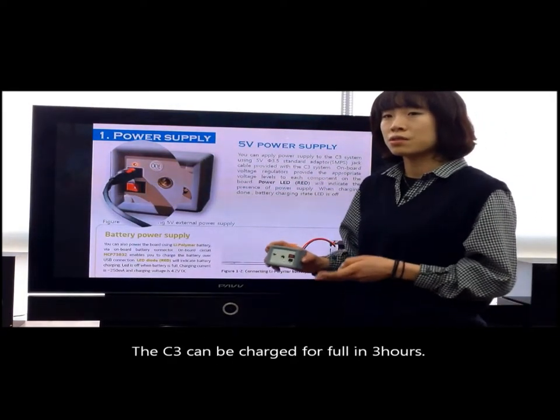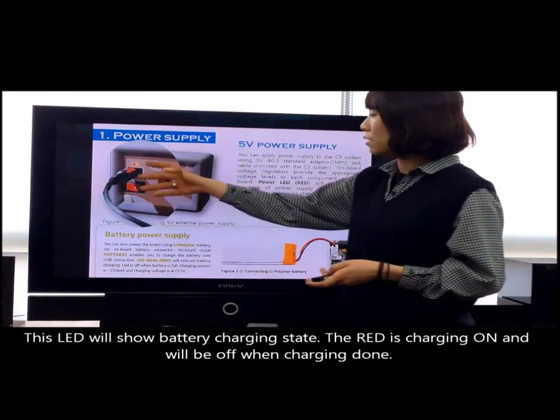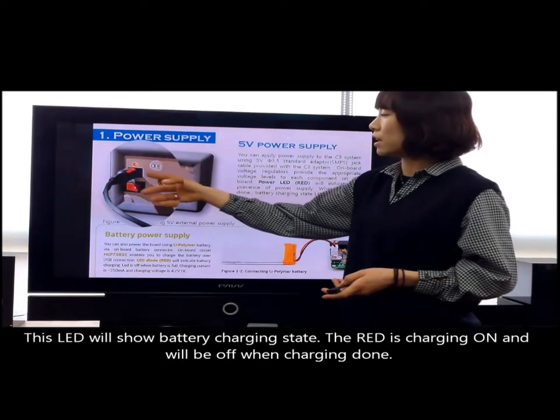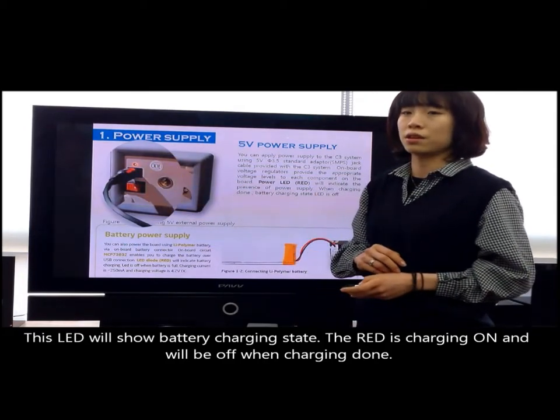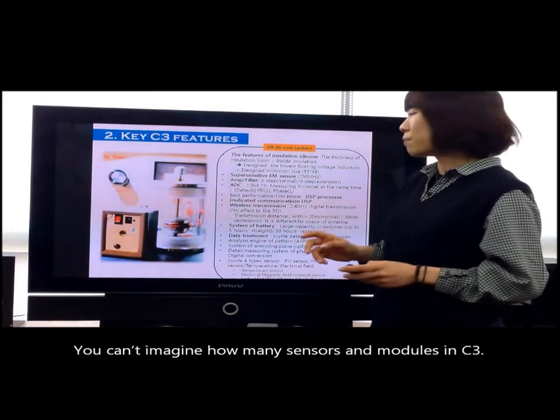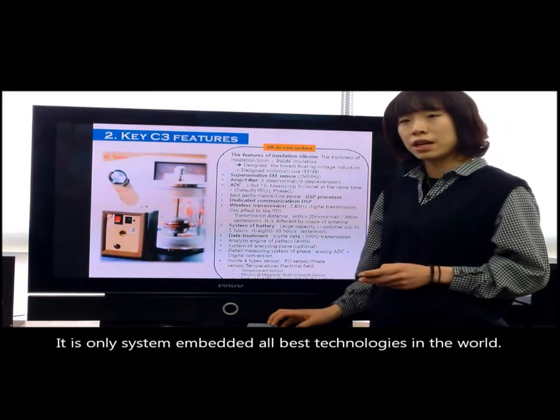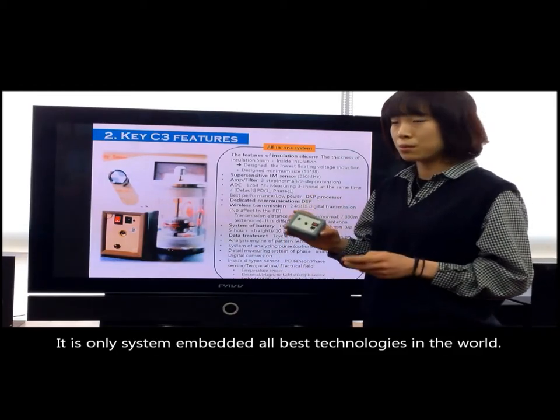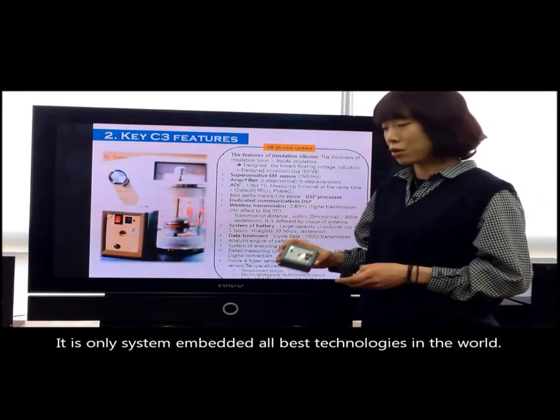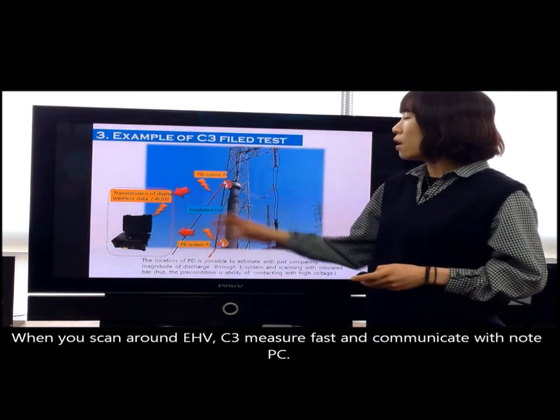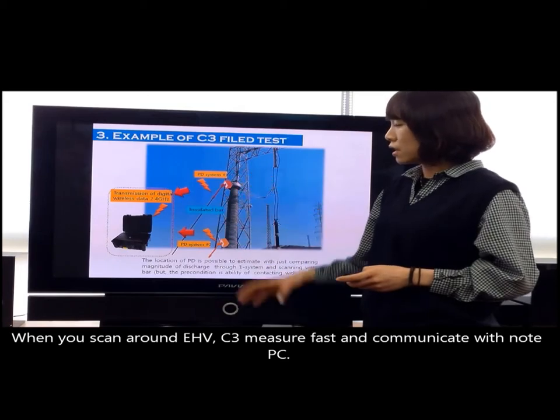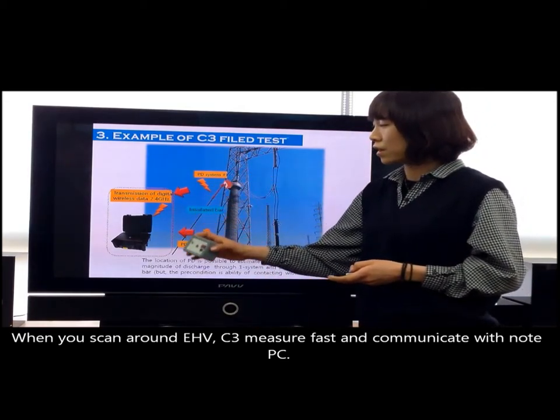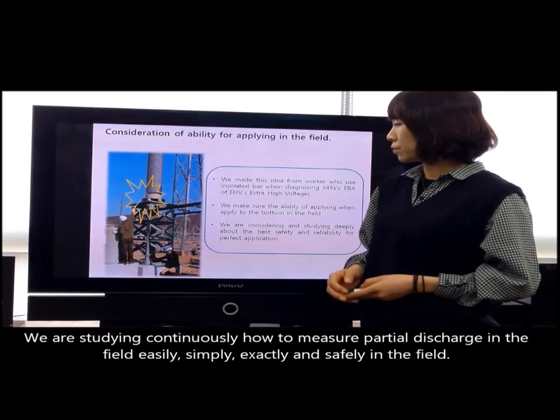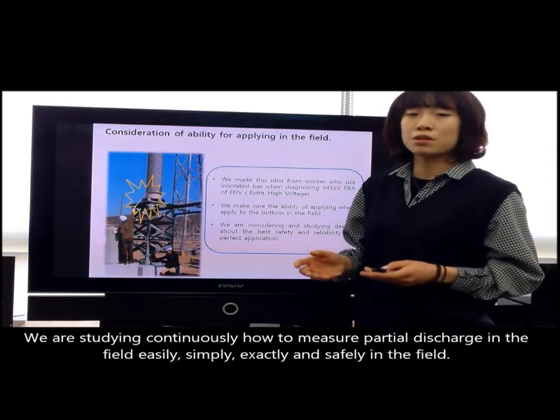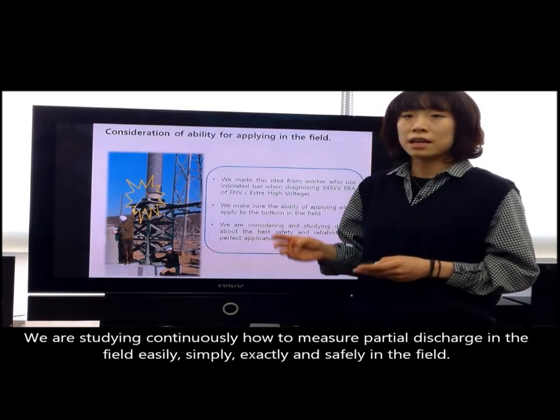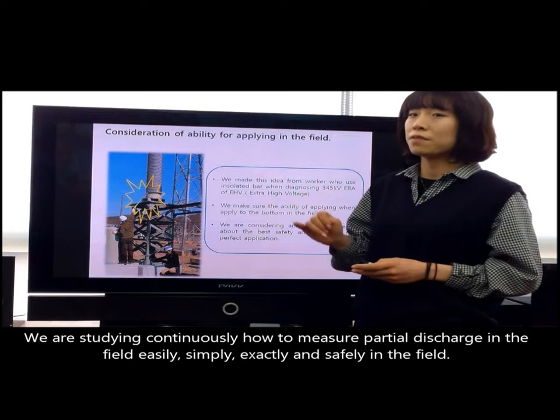And C3 can be charged fully in 3 hours. This LED shows the battery charging state. The red is charging on and will be off when charging is done. You can't imagine how many sensors and modules are in C3. It is the only system that embeds all the best technology in the world. When you scan around the extra high voltage, C3 measures fast and communicates with Note PC. We are studying continuously how to measure partial discharge in the field easily, simply, exactly, and safely.